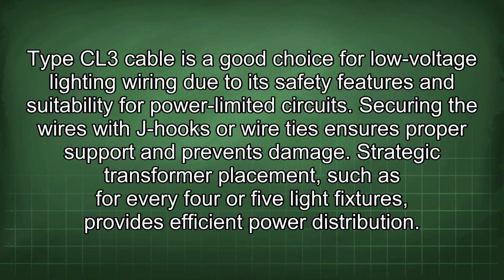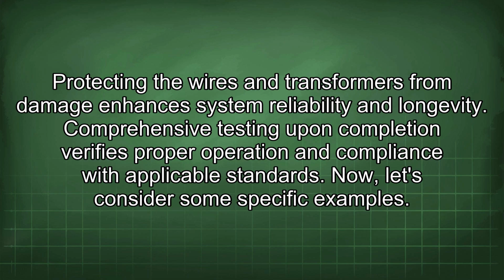Type CL3 cable is a good choice for low-voltage lighting wiring due to its safety features and suitability for power-limited circuits. Securing the wires with J-hooks or wire ties ensures proper support and prevents damage. Strategic transformer placement, such as for every 4 or 5 light fixtures, provides efficient power distribution. Protecting the wires and transformers from damage enhances system reliability and longevity. Comprehensive testing upon completion verifies proper operation and compliance with applicable standards.